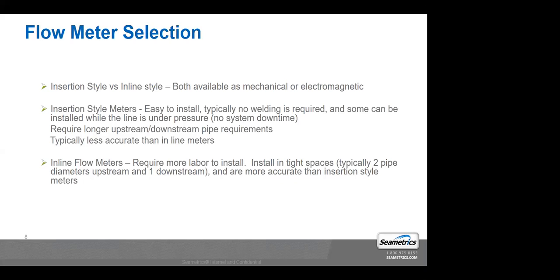Insertion style meters are obviously easier to install because you're not cutting a big section of your pipe out, welding mating flanges in, and adding the gaskets and maybe grounding rings and the bolts and everything to get that meter in line. So insertion meters are typically installed with either a saddle or a T, some type of a fitting that you're installing it into the pipe with. That's the advantage of an insertion meter, is the ease of installation. The disadvantage of them is they do require longer upstream, downstream pipe requirements, and they're less accurate than inline meters.